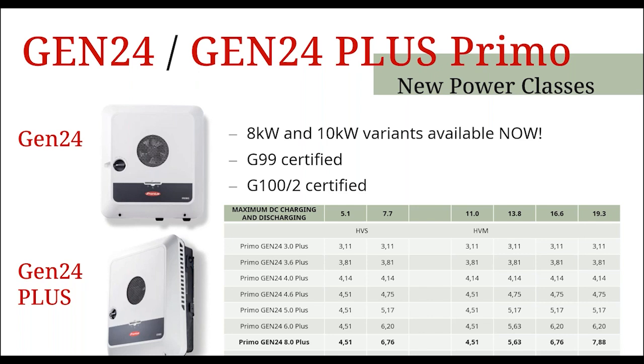Also, because we can oversize our inverters to 150%, we can install up to 15 kilowatts of solar onto one Gen24 Primo 10 kilowatt unit. So a really good sized PV system for a single phase installation.